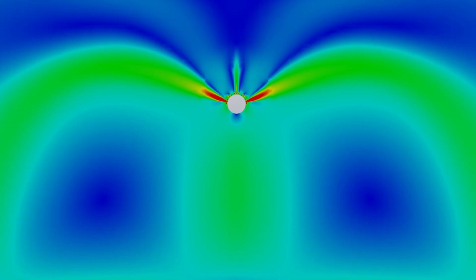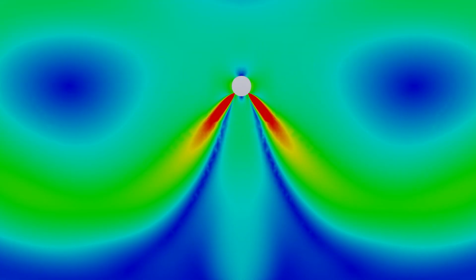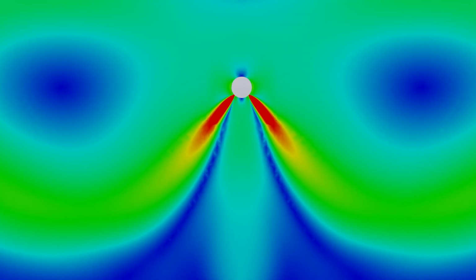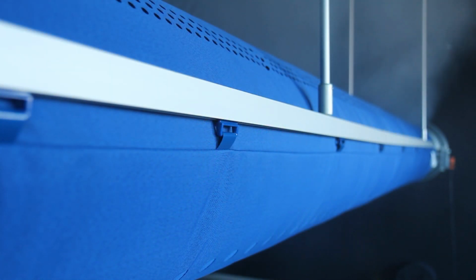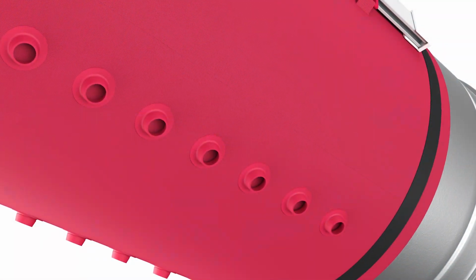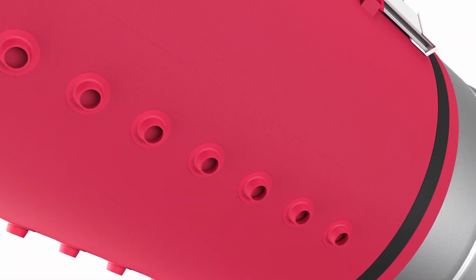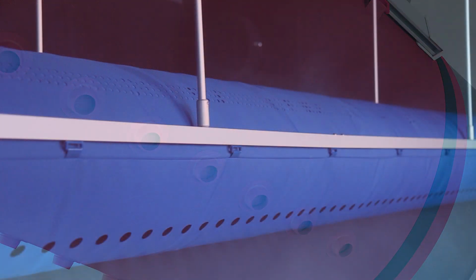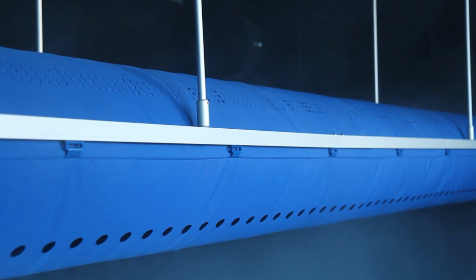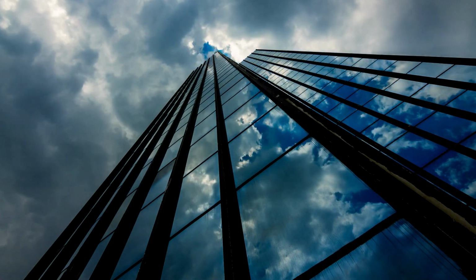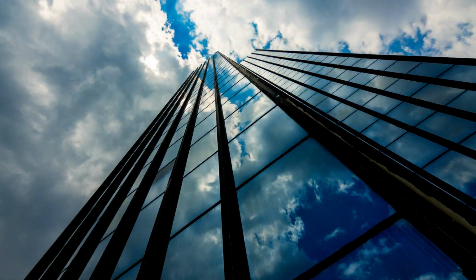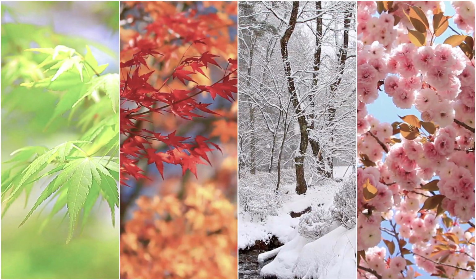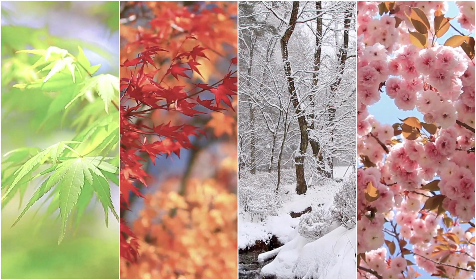The ideal air dispersion system is designed for optimal performance in both cooling and heating conditions, regardless of the temperature range. The challenge is that cold air falls and hot air rises. Thus, the nozzle size required to deliver heated air comfortably in the occupied zone results in too high air velocities to deliver the cooled air comfortably. The challenge is pronounced in areas of the world where the differences between summer and winter conditions is significant.